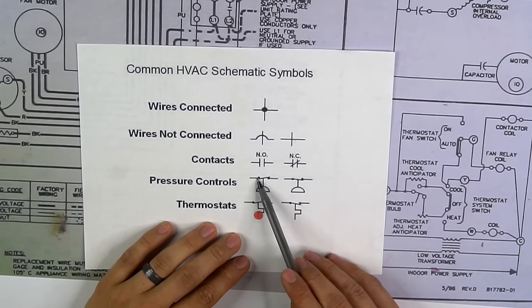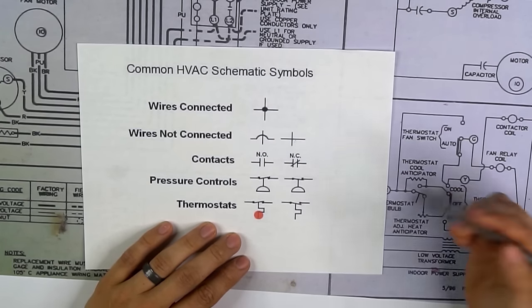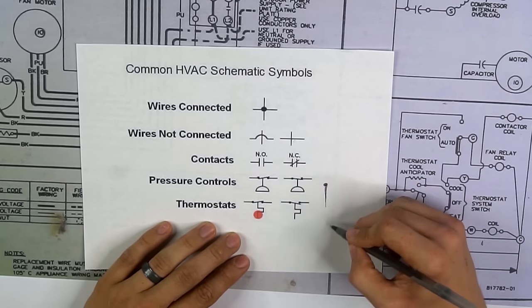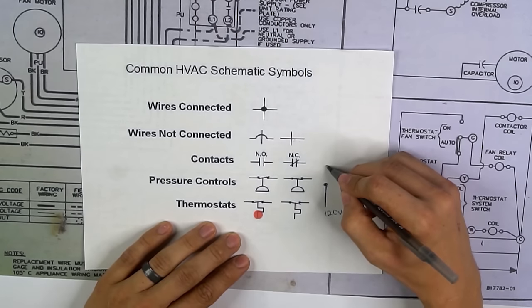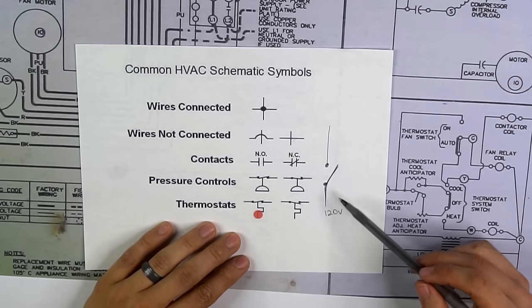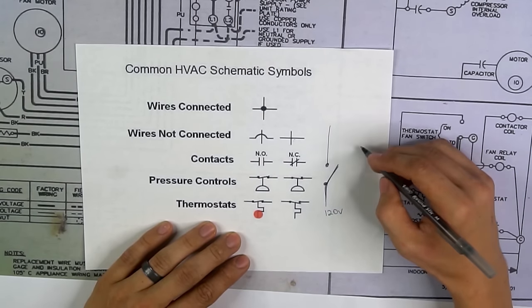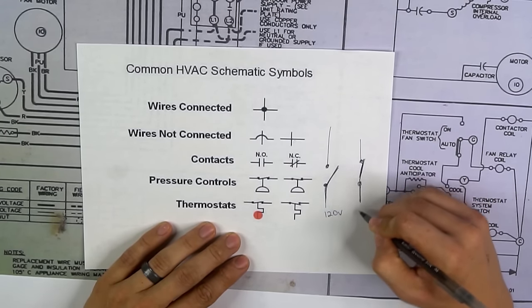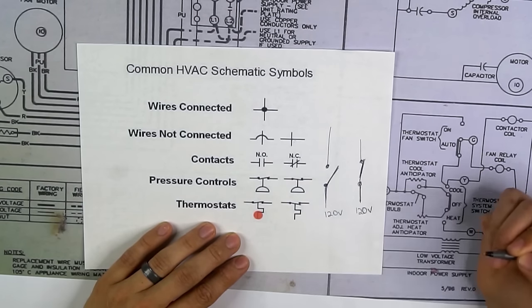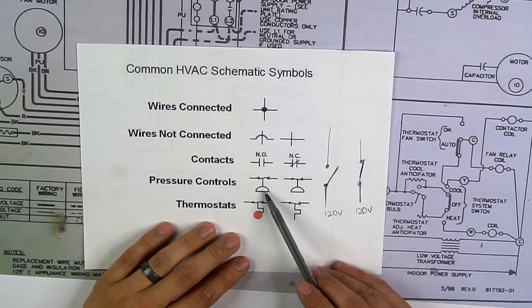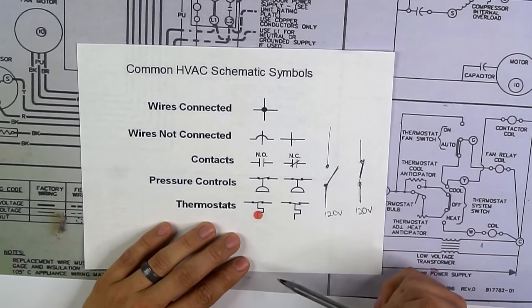Right here we have a wire, and right in the middle is a symbol for a switch. The plunger-looking thing is the symbol for pressure — this will typically be your low pressure cutoff or high pressure switch on the condenser unit. Most wiring diagrams are read left to right, just like reading a book. If the switch goes on top of the dot, it can only go up — that would be the high pressure switch, which interrupts the circuit if pressures get too high. If the switch is under the dot it can only go down — that's the low pressure cutoff, which trips if system pressures get too low.